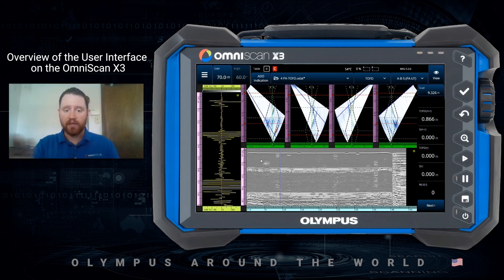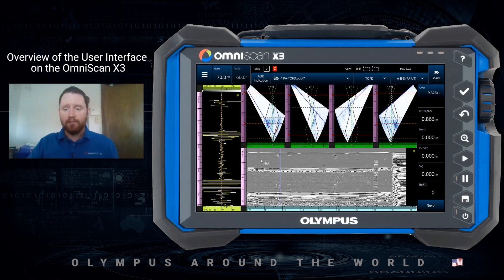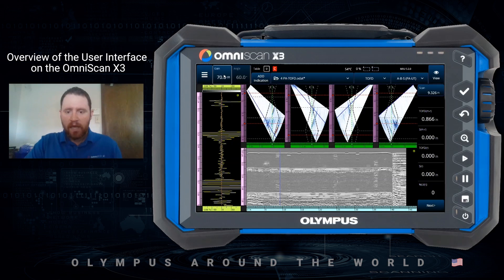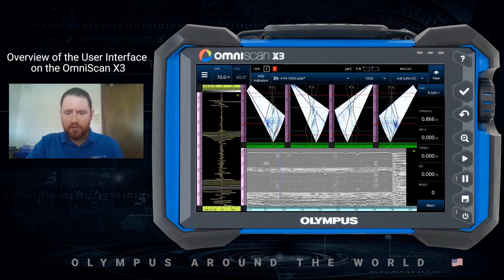Right off the bat, you can see some of that in the overall layout of the software. In order to take advantage of the larger widescreen format display on the instrument, we've had to move a few things around to accommodate a larger viewing area for our data. One of the first things you'll notice is changes to the toolbar across the top, mainly with readings being moved from the top of the display over to the right-hand side. To the left of those readings, we have the viewing area for your data — a multi-group data file with phased array channels and a channel of TOFD running simultaneously. Across the top we have our typical toolbar.